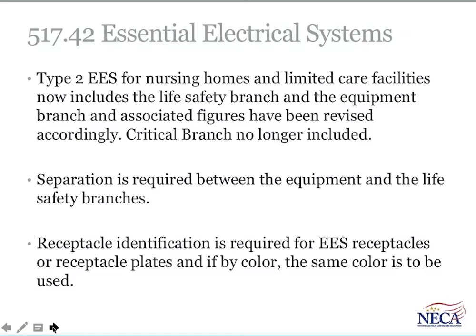Separation is still required between the equipment and life safety branches, and once again, clarification there that identification is required for essential electrical system receptacles or the plates, and if it's by color, the same color needs to be used. Red is often the color to be used, but neither the NEC nor NFPA 99 specifies a color.